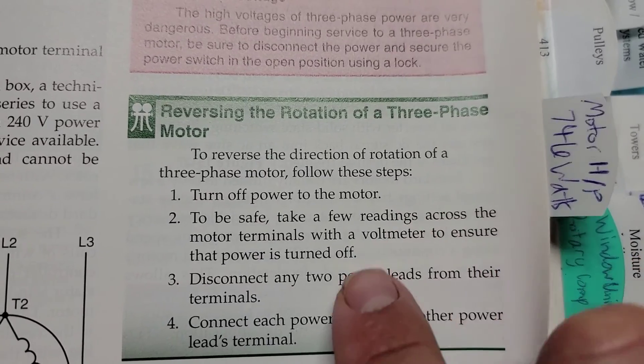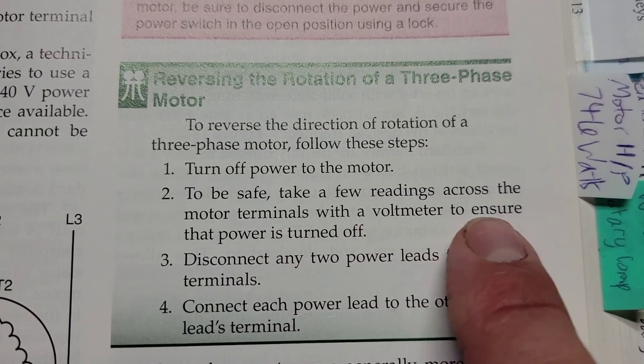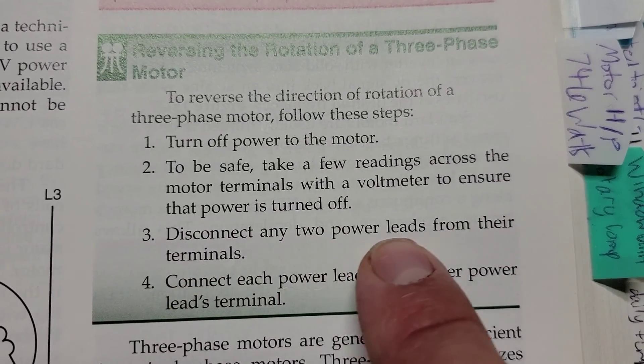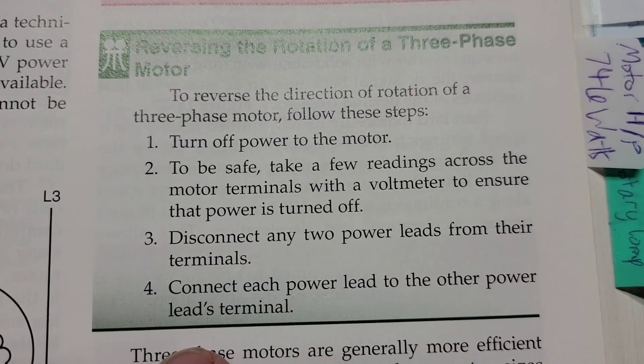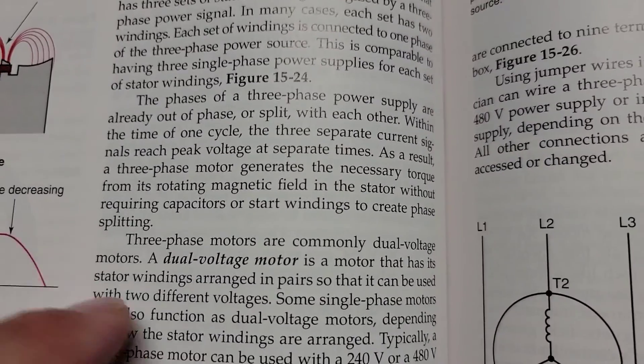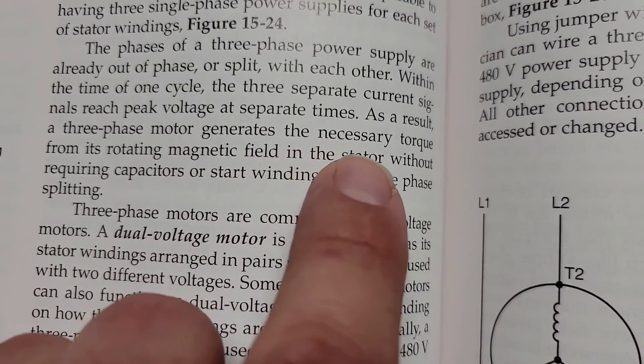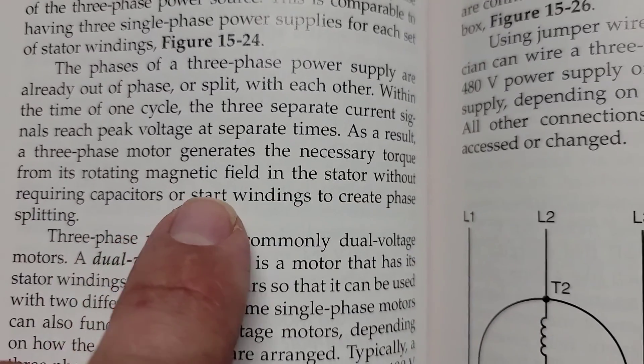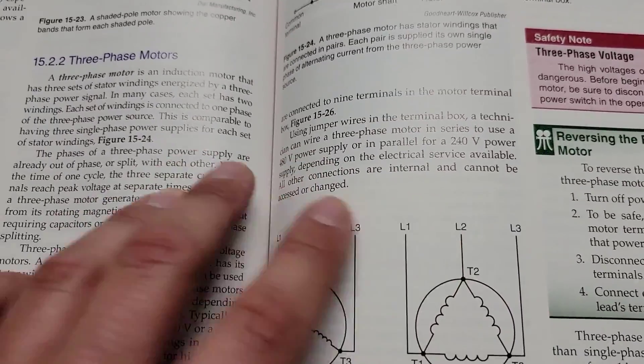We need to stop the video if you need to, because this is a great step-by-step for knowing how to reverse the direction of rotation of a three-phase motor. Turn off power to the motor. To be safe, take a few readings across the motor terminals with a voltmeter to ensure that power is turned off. Disconnect any two power leads from their terminals and connect each power lead to the other power lead's terminals. The three-phase motor generates the necessary torque from its rotating magnetic field in the stator without requiring capacitors or start windings to create phase splitting — and that is why three-phase motors don't require capacitors.